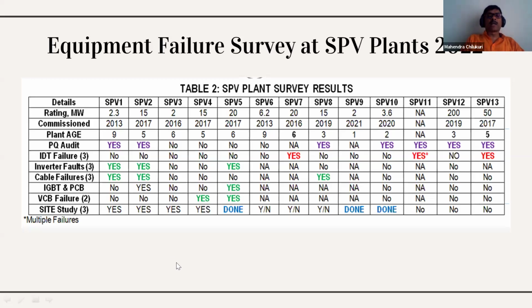So it's not just about inverter duty transformer failure. Inverter faults occur, cable failures occur, IGBT and PCB failures occur, VCB failures occur. In fact, VCB failure is the biggest problem.